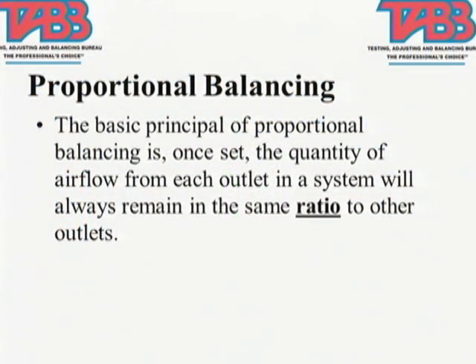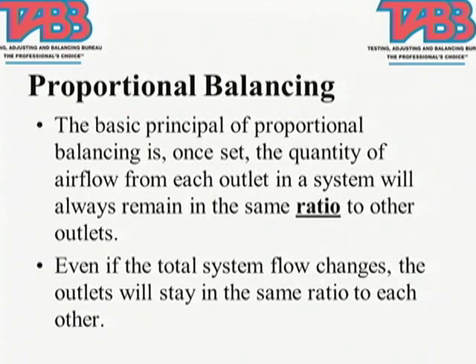The idea behind this is once you set two valves or two dampers in the same position with the same flow ratio, no matter what you do to the rest of the system, those flows will vary together. When we adjust damper number 3, after we've set 1 and 2, they rise and fall together proportionally to each other. That's where the term comes from. So we set it and we keep working our way right down the line for that. Even if the total system flow changes, they still remain in proportion to each other.